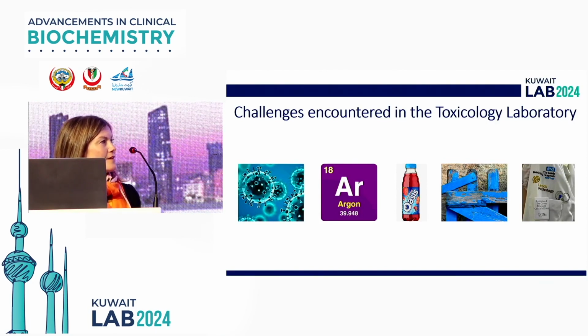And the other enemy to us really in the ICP-MS lab is that the senior technician who runs the ICP-MS lab is extremely organized and extremely efficient. And he loves having a clean slate at the end of the day. So if there's any work, he will try and get through it. But if you're running out of argon, then that is not what you need. Basically, we realized that we really need to keep an eye on how much argon we've got left. So after 2 weeks, we start monitoring how much argon we're using on a daily basis, just in case the driver isn't able to turn up. And we joke about it, but it is a real thing.